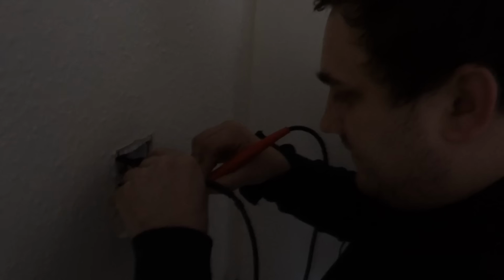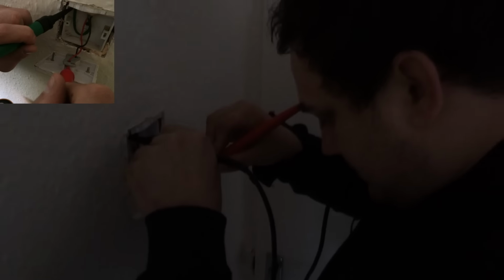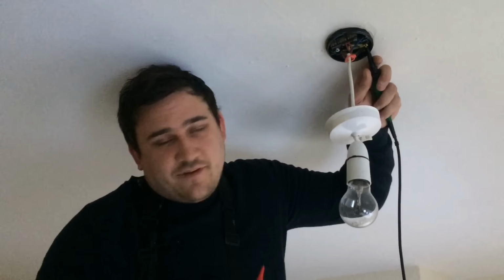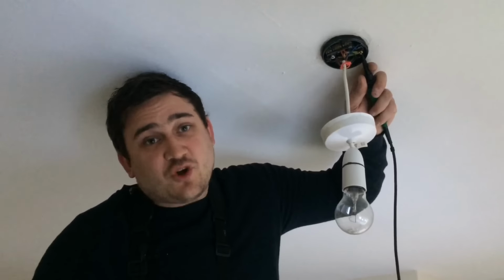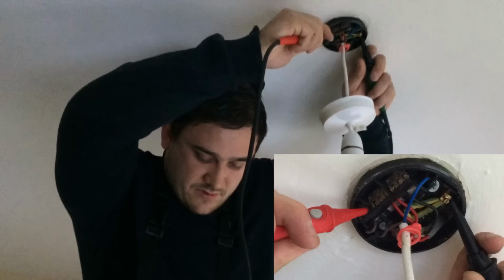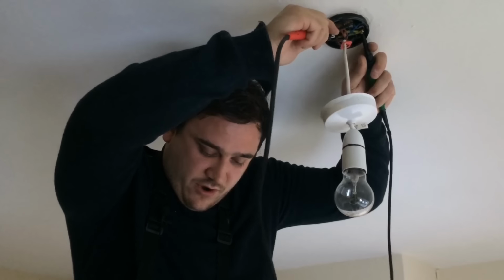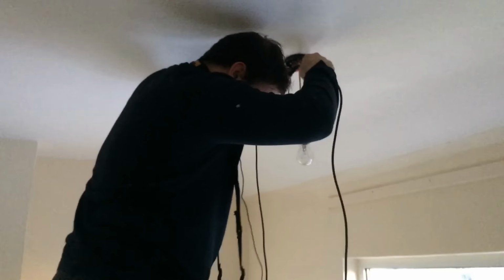Going on to my CPC and my line conductor. Get a reading of 1.68. I'm now at the light fitting. I'm just checking between my CPC and my switching line. I get a reading of 1.46. Now I will operate the switch to prove polarity, that it switches. Now I have an infinite reading, which proves polarity. We found our highest reading was 1.64 on the upstairs lighting circuit.